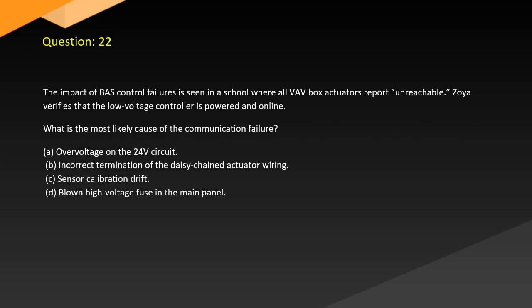Question 22. The impact of BAS control failures is seen in a school where all VAV box actuators report unreachable. Zoya verifies that the low-voltage controller is powered and online. What is the most likely cause of the communication failure? A. Overvoltage on the 24-volt circuit. B. Incorrect termination of the daisy-chain actuator wiring. C. Sensor calibration drift. D. Blown high-voltage fuse in the main panel.